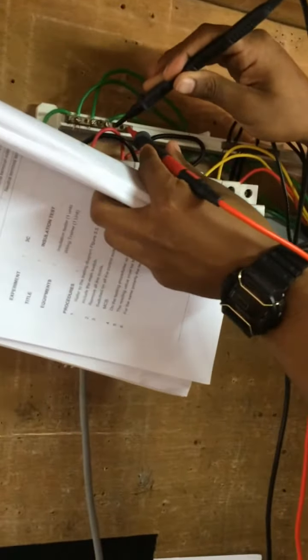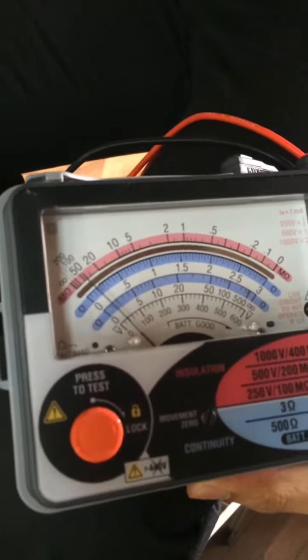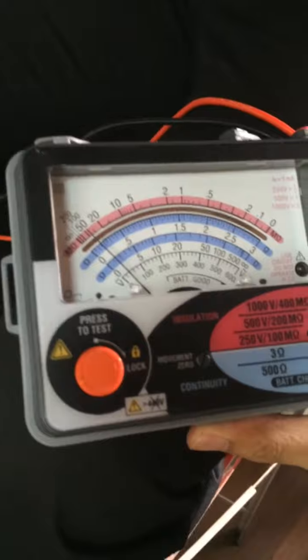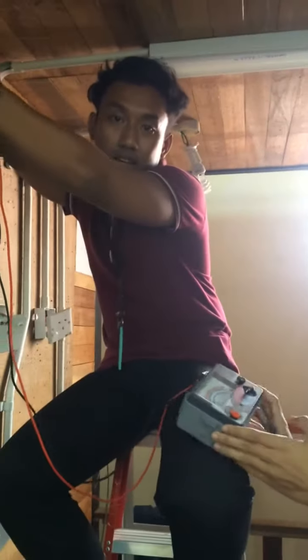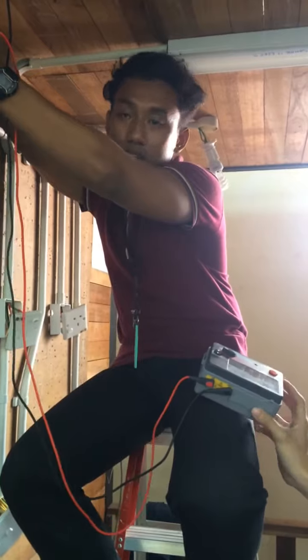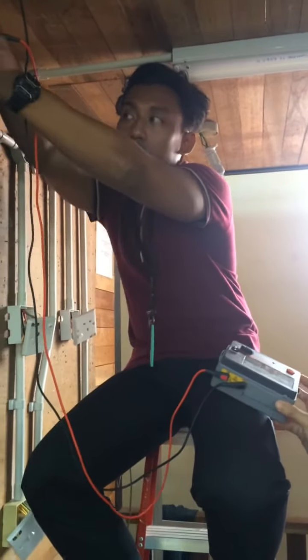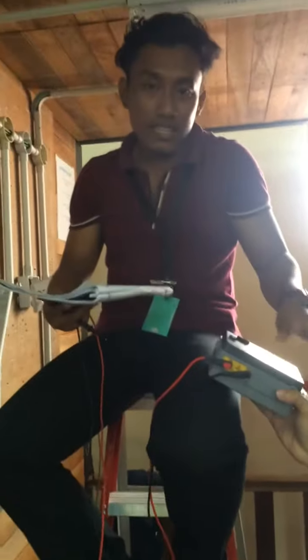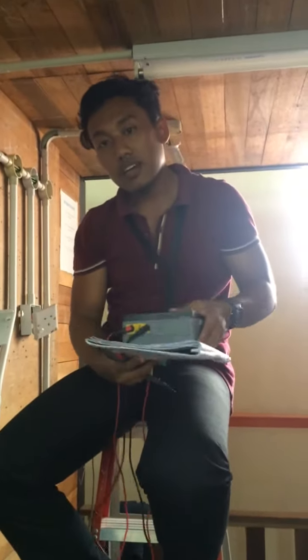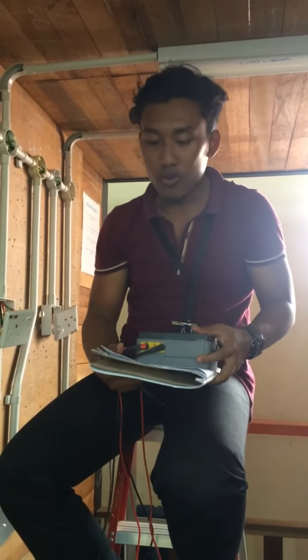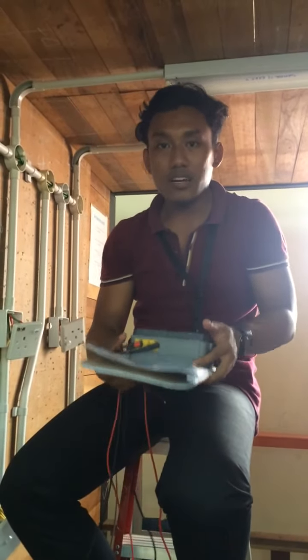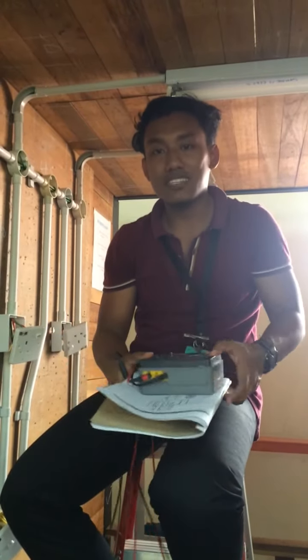And then lastly, let's change to another point, earth to earth, for another same point. The meter reading also shows that the reading is lower than 1 meg, because for the same point, the reading must be lower than 1 meg. So the condition of the circuit is good. So our testing for the insulation tester is finished here. Thank you for watching our video and good luck to you all for making this insulation test. Thank you.